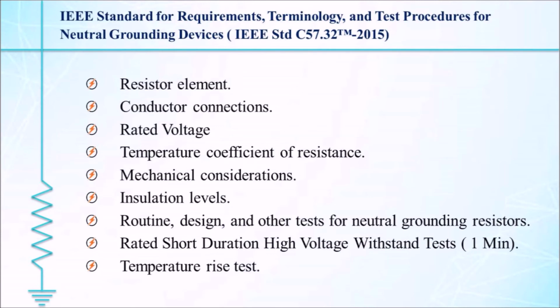Routine, design and other tests for neutral grounding resistors. A routine test is a test made on each and every unit of a specific design and is primarily a verification of quality. Routine tests shall be made on all neutral grounding resistors in accordance with the requirements. A design test, also referred to as a type test, is a test carried out on a single unit of a specific design and is primarily a verification of the ability to meet in-service application requirements.